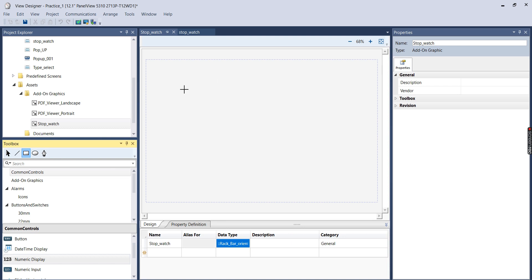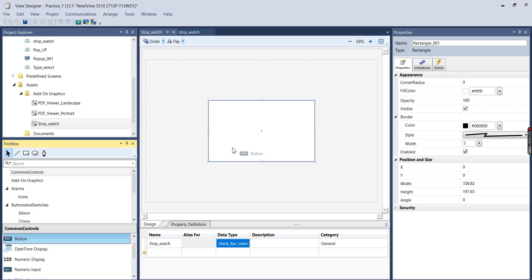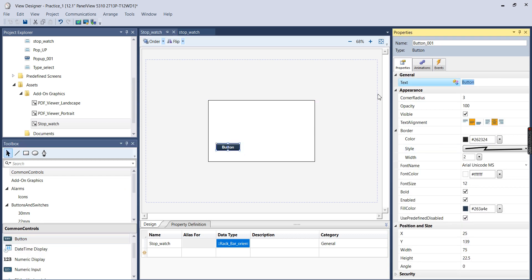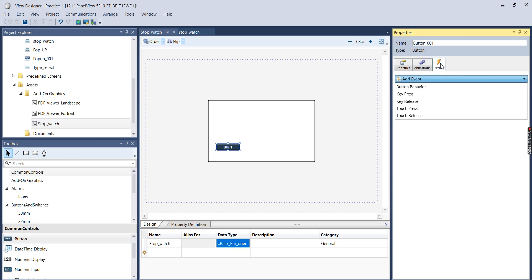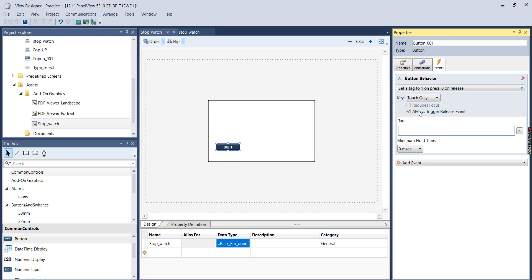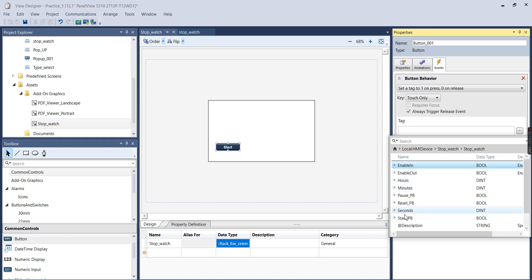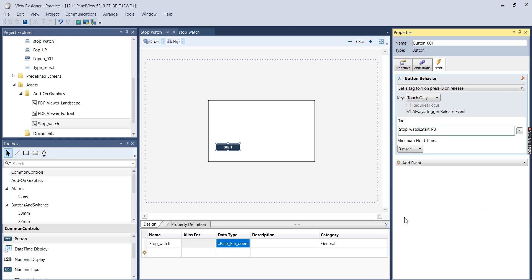So I'm just going to come over here and drag and drop a box. I'm going to add a button, I'll name it Start. I'll go over here to Events and add a button behavior. And I'll make it select, set a tag to 1 on press, 0 on release. And I will select, I'll go down to Stopwatch and Start PB. So these are not actual controller tags, these are just fields of the UDT. So this isn't a tag, this is the data type, and then this is the Start PB field within that data type.